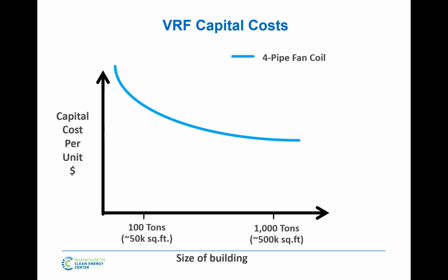Years ago, I think VRF's been in the US for a little over 15 years officially. It was used on smaller projects, renovations. You weren't doing whole building solutions with it. Whereas if you fast forward to now, doing a 200,000 square foot building is not uncommon. Even in this area, in the Boston area, across the country, doing that size building is not uncommon. So we see the equipment for VRF getting into larger and larger applications as the technology grows to meet the demands of the market, but also because of this capital cost situation here.